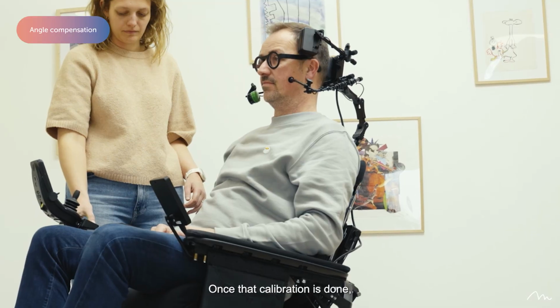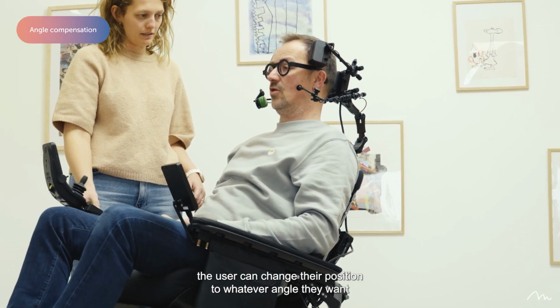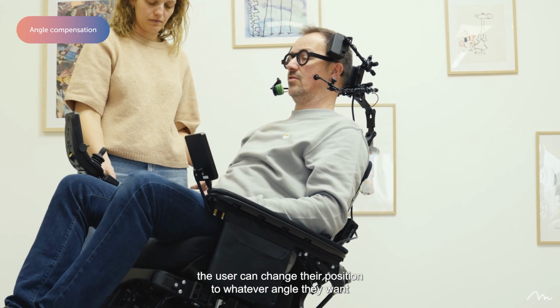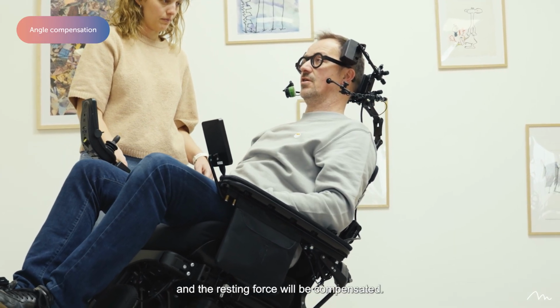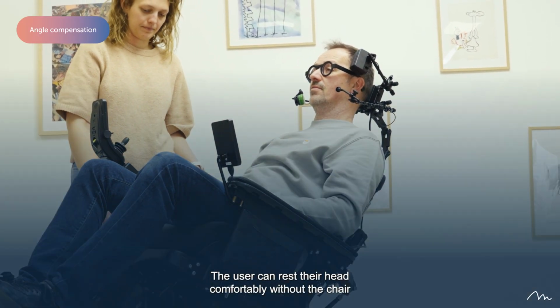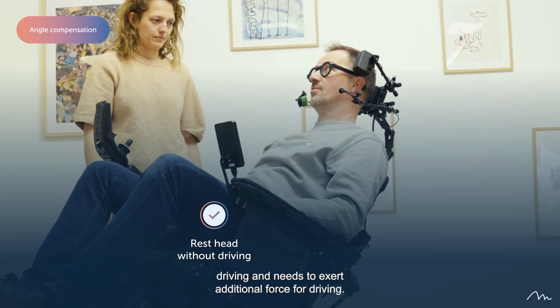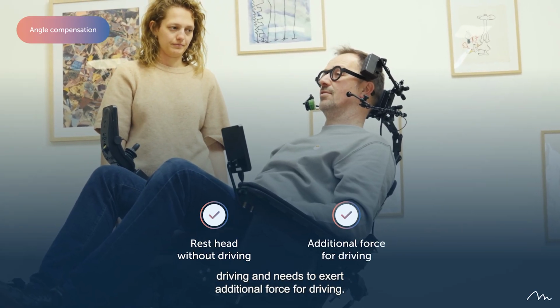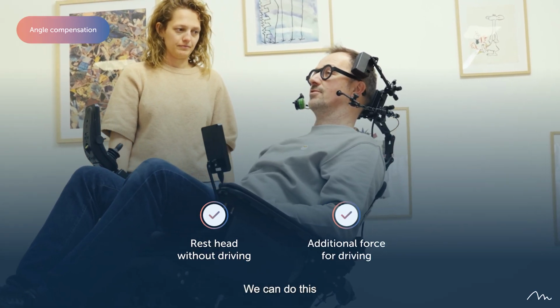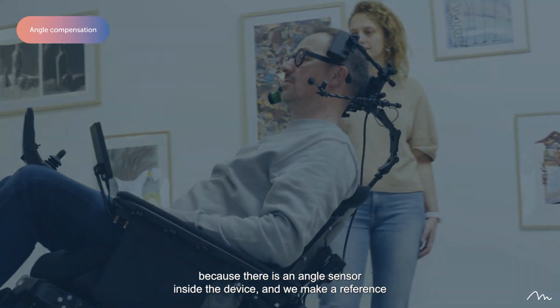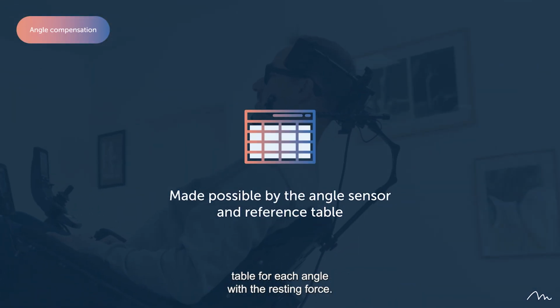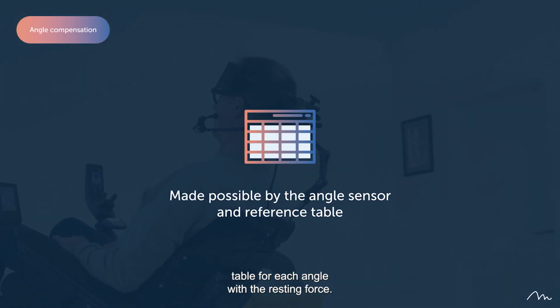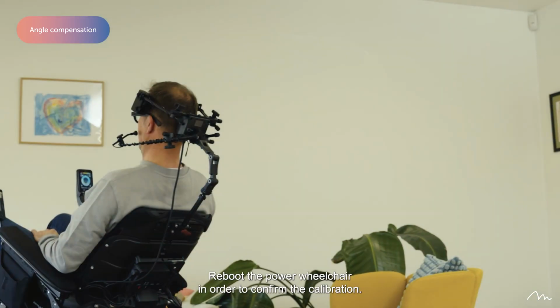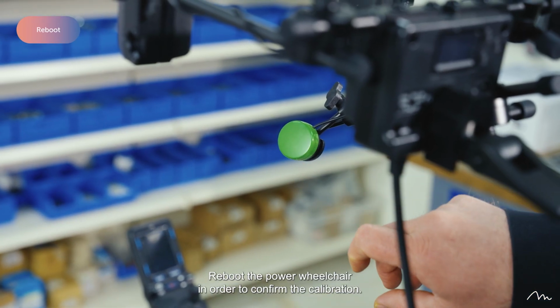Once that calibration is done, the user can change their position to whatever angle they want, and the resting force will be compensated. The user can rest their head comfortably without the chair driving and needs to exert additional force for driving. We can do this because there is an angle sensor inside the device, and we make a reference table for each angle with the resting force. Reboot the power wheelchair in order to confirm the calibration.